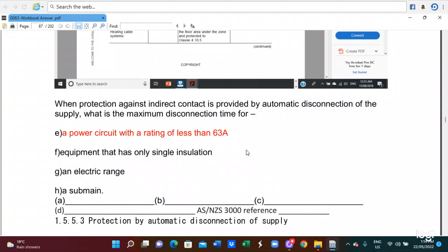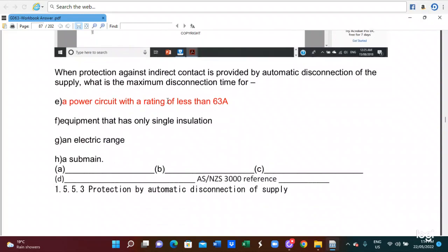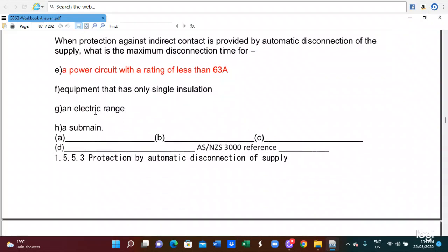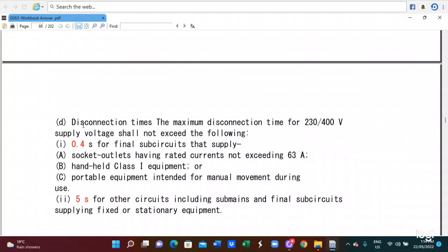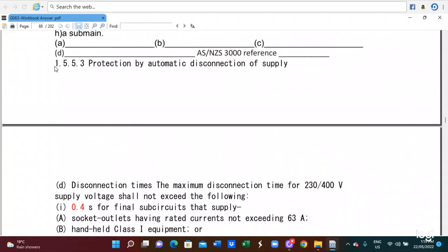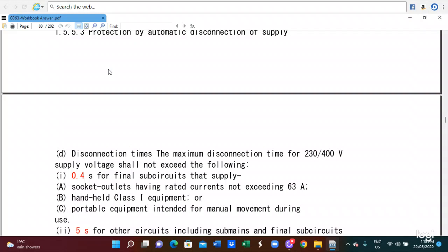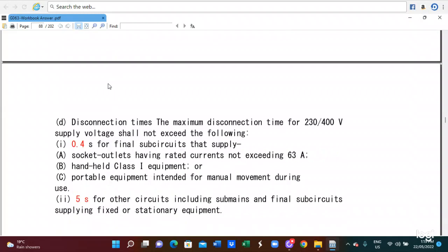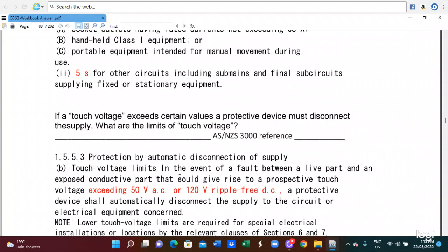Protection against indirect contact is provided by the automatic disconnection of supply. So the disconnection time for the power circuit with rating less than 63 amps. So these are the protections. In this case, I would have to utilize this clause, AS/NZS 3000 clause 1.5.5.3, the protection by the automatic disconnection of supply. It is 0.4 seconds for the final circuit, 5 seconds for the other circuit.